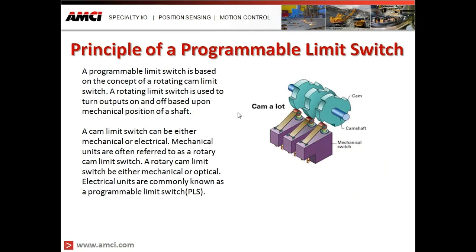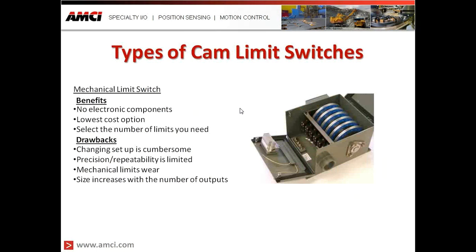A programmable limit switch is based on the concept of a rotating cam limit switch, similar to what you would see in your car. A rotating limit switch is used to turn outputs on and off based upon the mechanical position of a shaft. A cam limit switch can be either mechanical or electrical. Mechanical units are often referred to as rotary cam limit switches, which can be either mechanical or optical. Electrical units are commonly known as programmable limit switches, or PLS.